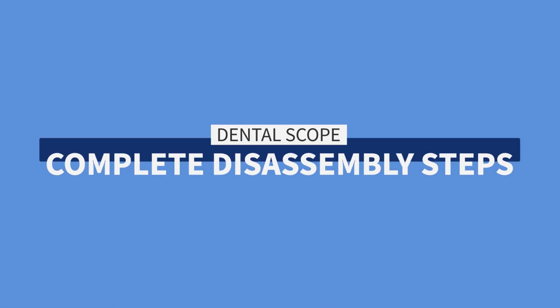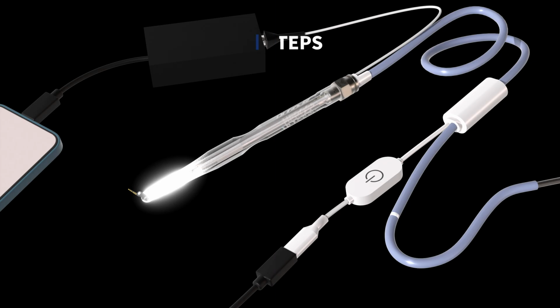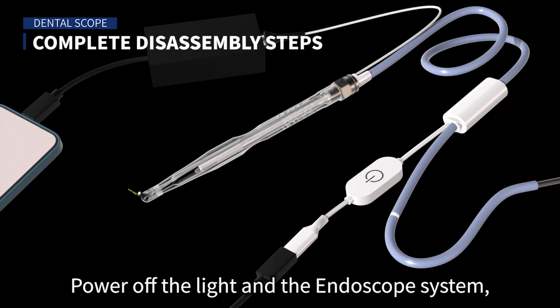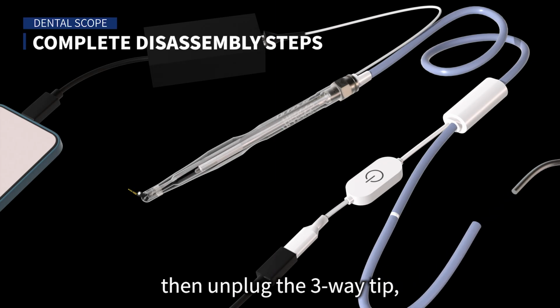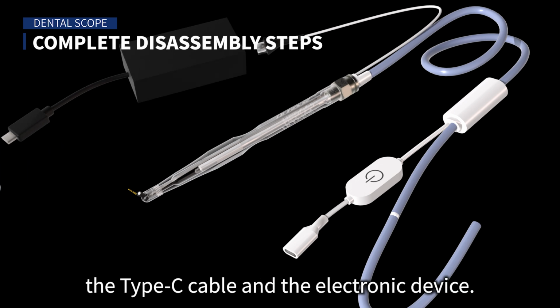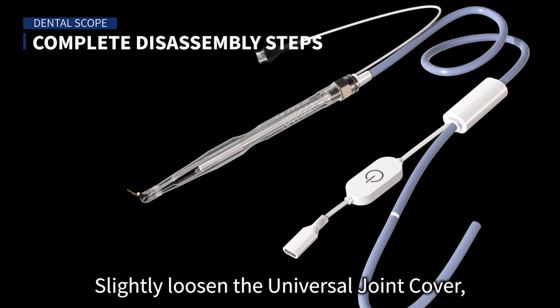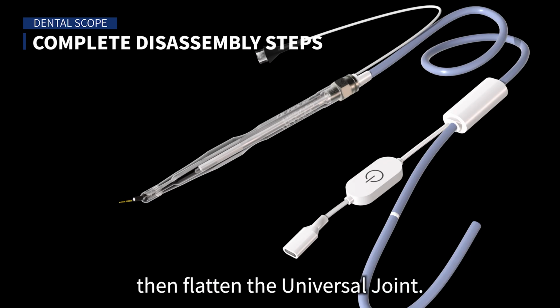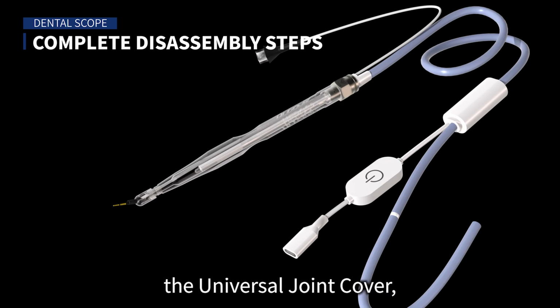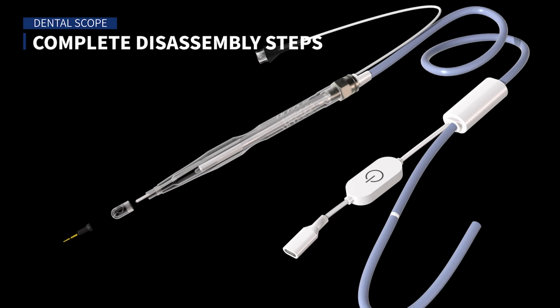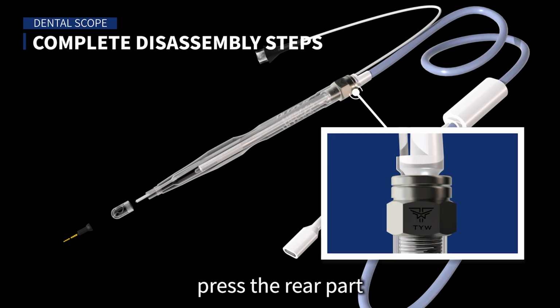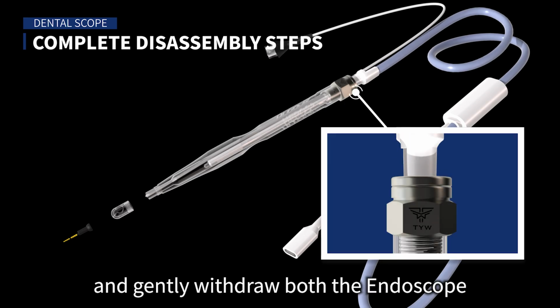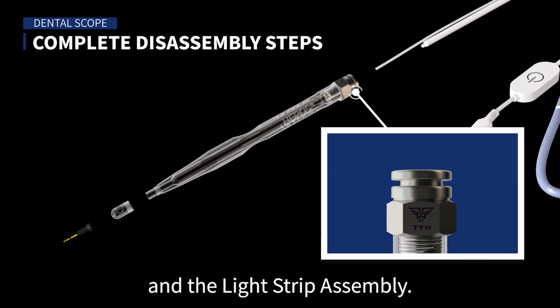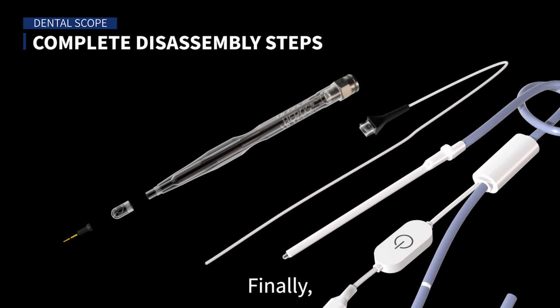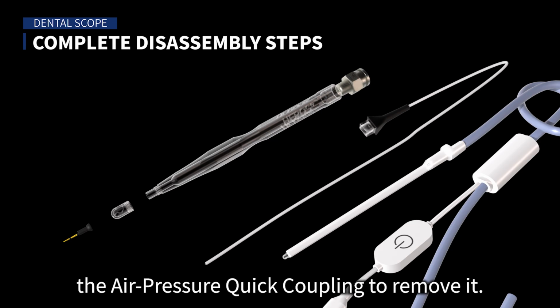Dental scope complete disassembly steps. Power off the light and the endoscope system, then unplug the three-way tip, the Type-C cable and the electronic device. Slightly loosen the universal joint cover, then flatten the universal joint. Disassemble the pen, the universal joint cover, and the universal joint. While holding the pen steady, press the rear part of the air pressure quick coupling, and gently withdraw both the endoscope and the light strip assembly. Finally, please loosen and unscrew the air pressure quick coupling to remove it.